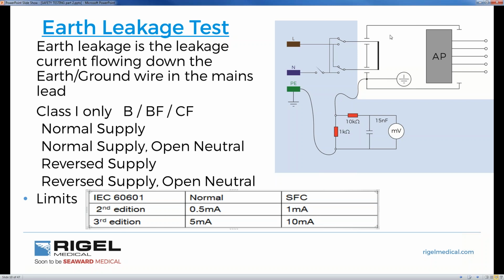So if I have any stray capacitance or dielectric resistance within the medical device, what is happening is we have 230 volts in on our live. Bear in mind these relays are our single fault conditions: normal supply, open neutral, reversed. We have 2 relays at reverse, and then we have reversed supply open neutral. So internally within the Rigel, we adhere to 60601 with a number of relays opening in a sequential manner to provide the single fault conditions. So if I have mains input of 230 volts coming in on your live, the current would flow through the live conductor to the neutral conductor to provide a functional amount of current for the medical device to operate as its intended purpose of use, as the manufacturer wanted the device to be powered.